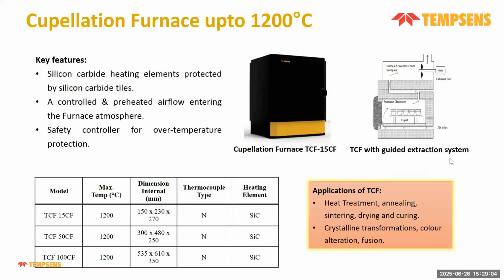Then we have a cupellation furnace. So the cupellation furnace is used where you have to anneal gold at high temperature. Basically, we use silicon carbide because gold has some lead content in it, so it can corrode the heating element. That's why the silicon carbide heating element is provided, protected by silicon carbide tiles, and we put some controlled and preheated airflow entering the furnace. You can see from the diagram that there is an air inlet with controlled, preheated airflow, and then there is an exhaust vent with an exhaust fan which will take out the fumes from the furnace. So this is basically the TCF with guided extraction system.